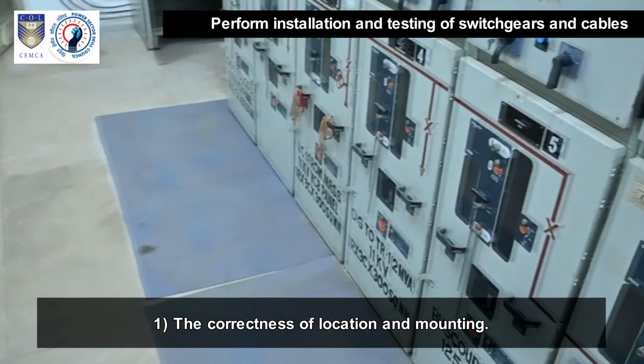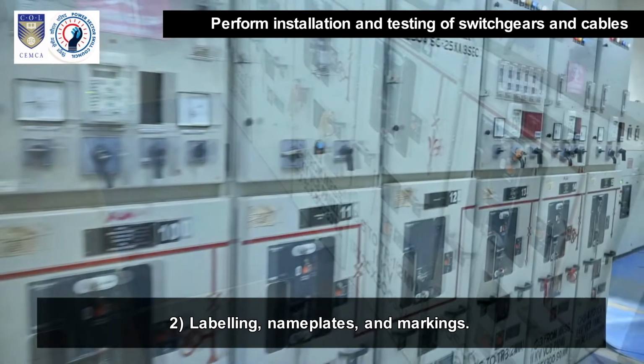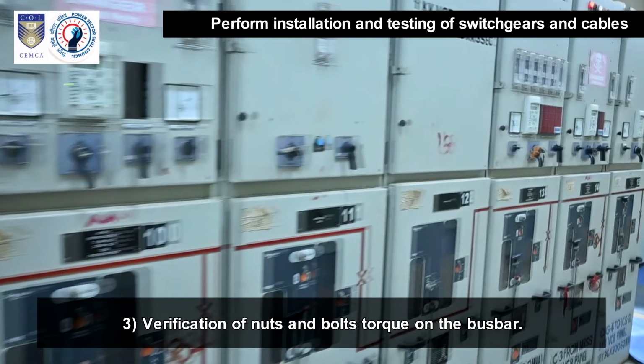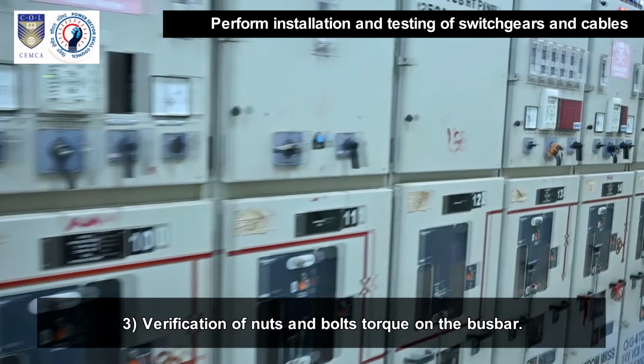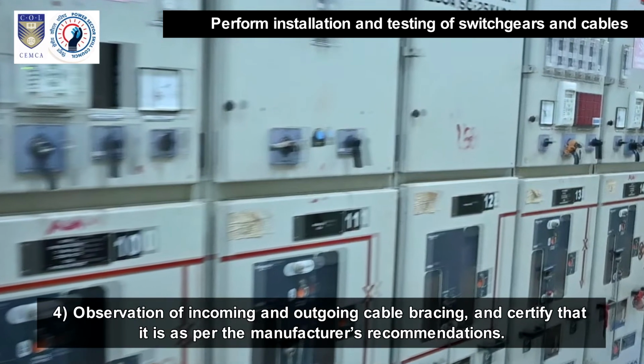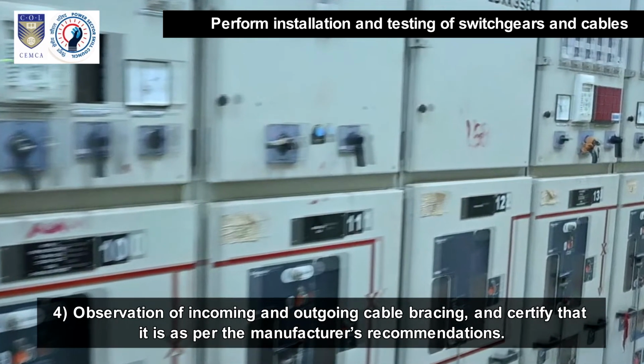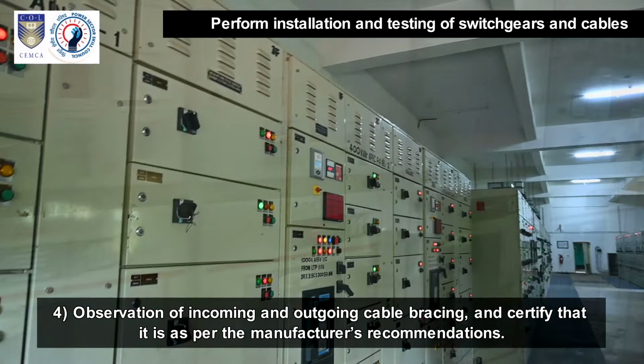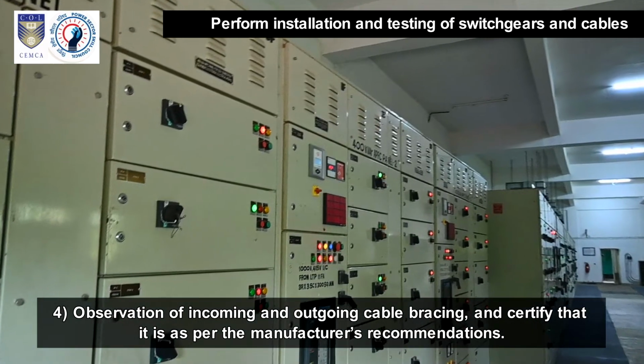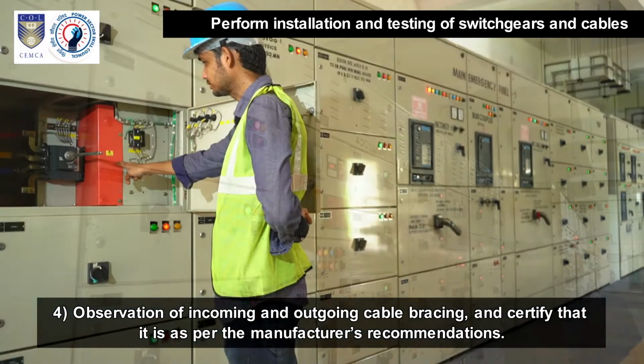1. The correctness of location and mounting. 2. Labeling, nameplates and markings. 3. Verification of nuts and bolts torque on the bus bar. 4. Observation of incoming and outgoing cable bracing, and certify that it is as per the manufacturer's recommendations.